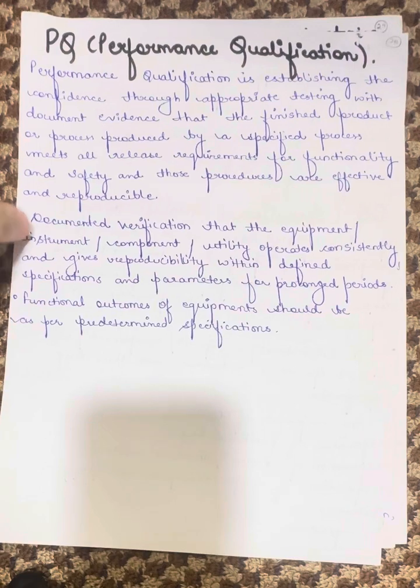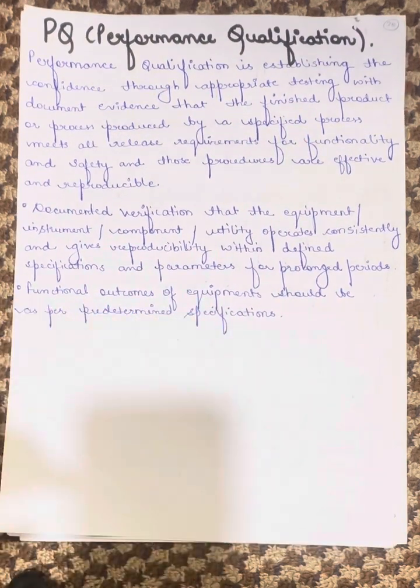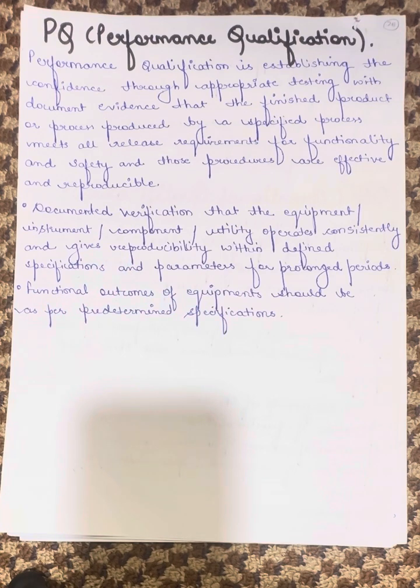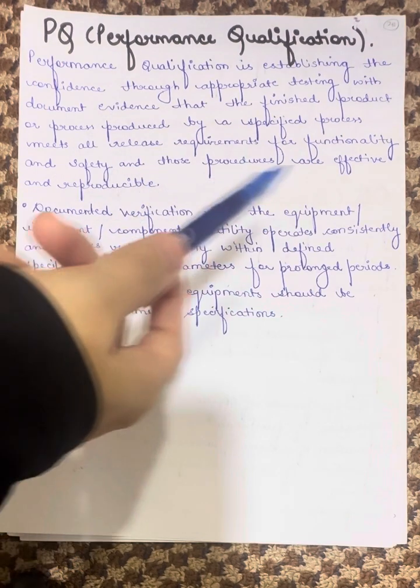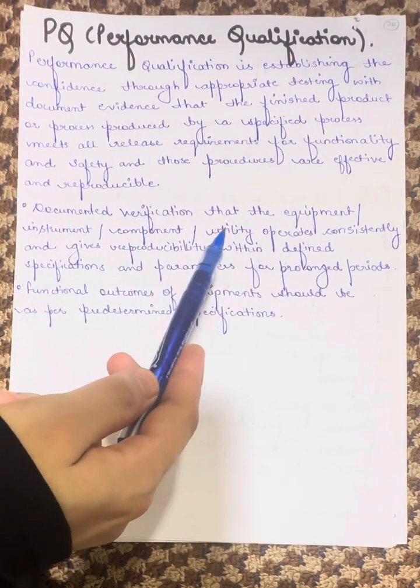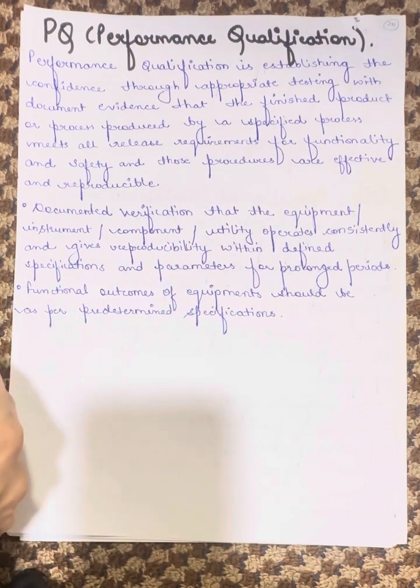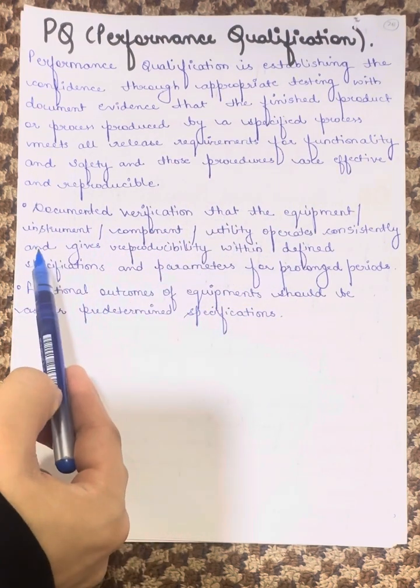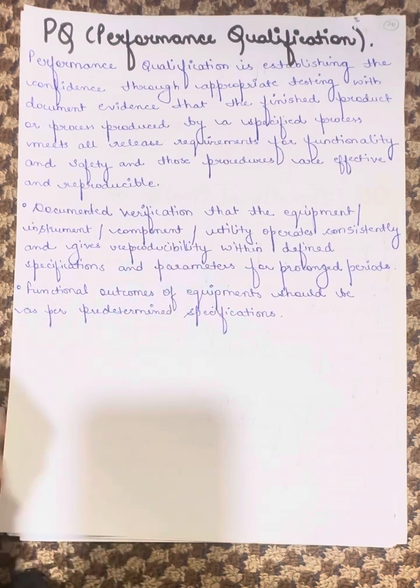The last is PQ, which stands for Performance Qualification. Performance qualification is establishing the confidence through appropriate testing which provides document evidence that the finished product or the process produced by a specified process meets all the release requirements for functionality and safety, and those procedures are effective and reproducible. Documented verification that the equipment, instrument or component utility operates consistently and gives reproducibility within the defined specification and parameters for a prolonged period.